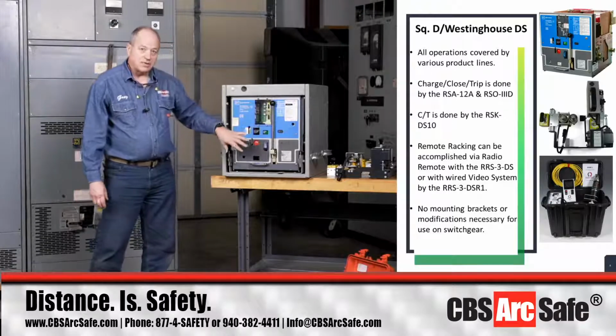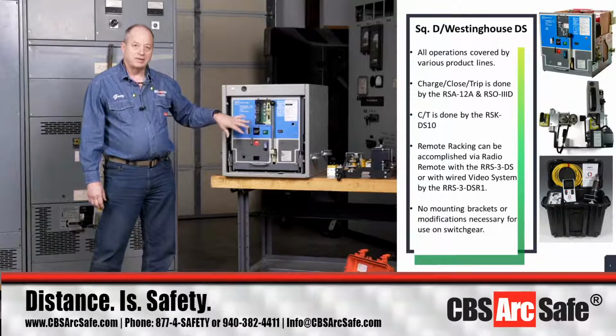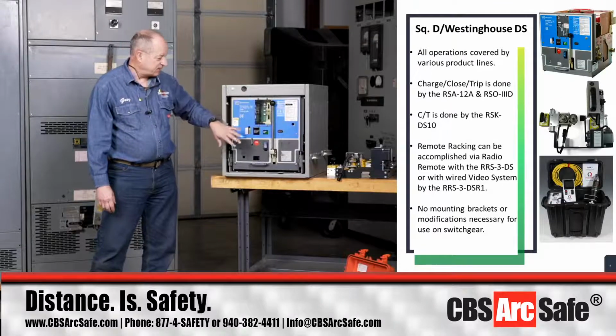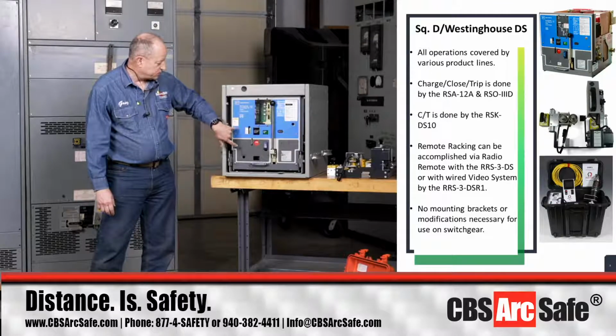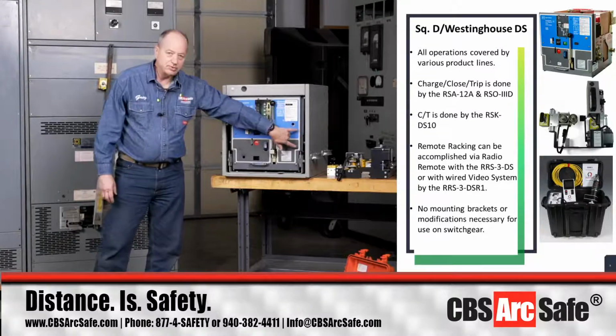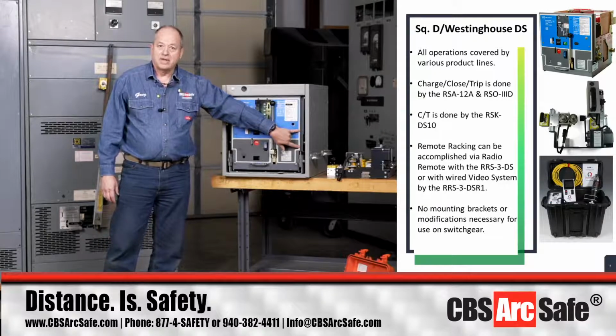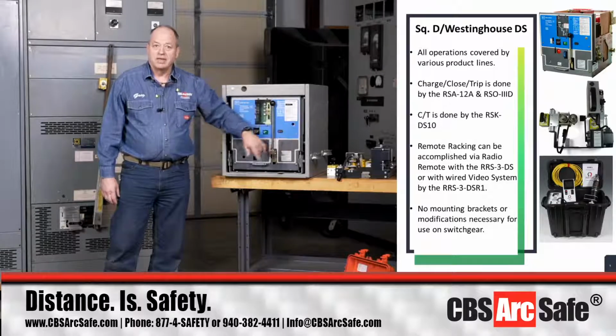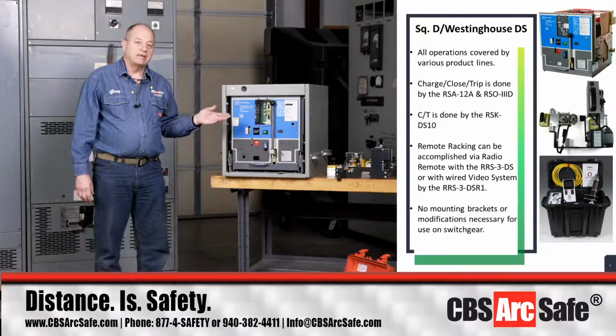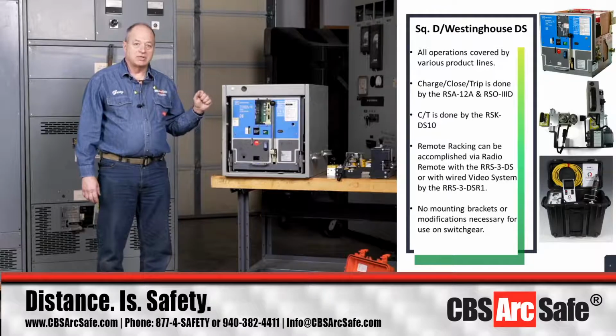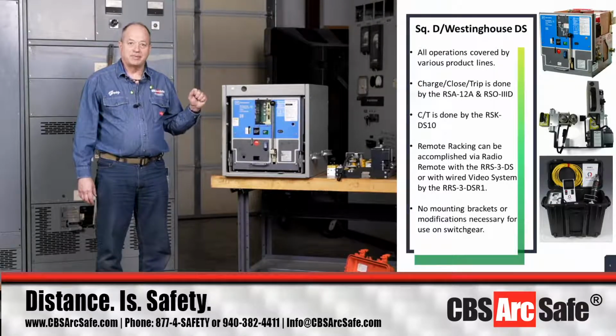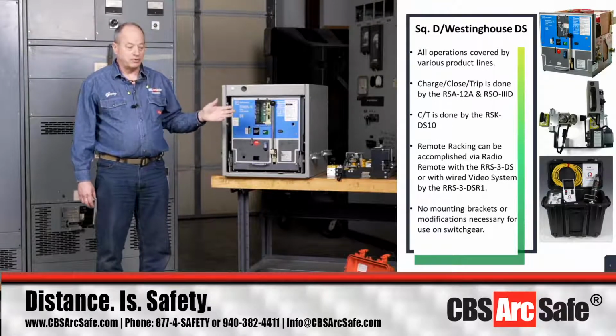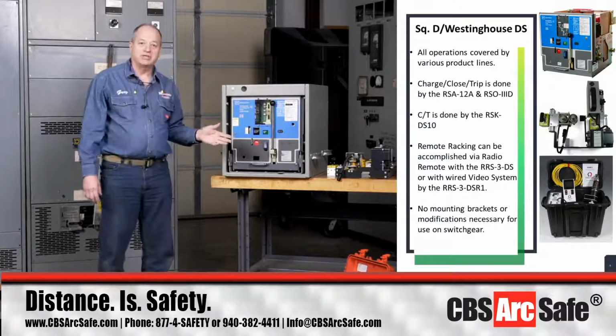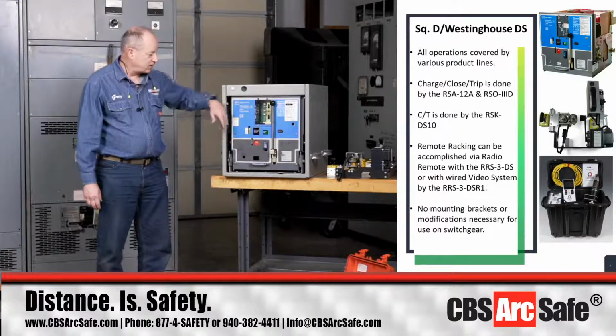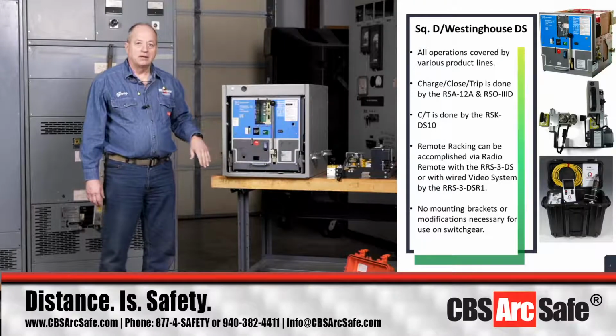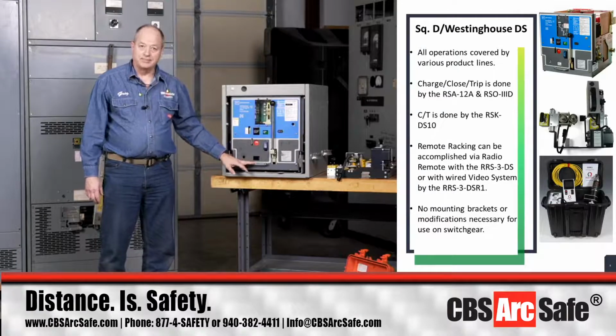Now, just to describe a couple variations: a DS breaker will always have a similar face, but if it was made in early 1972, it may have two handles over here on the side, so we have a different variation to deal with there. These breakers were also licensed to be made by Mitsubishi, and we found these in the Middle East and a couple other places where you open the cubicle door and think, that's a DS breaker, but it says Mitsubishi on it. They'll have the handles on the side instead of down here at the bottom.